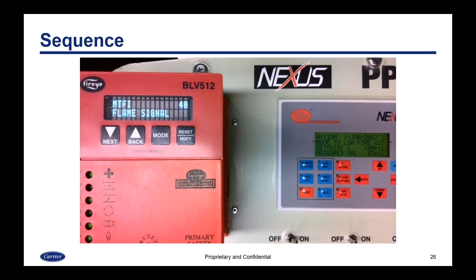So that's one thing to keep in mind, is if you're going to use something like revert to pilot, you're going to want your ignition and your low fire positions to be the same, because it's going to have to be able to light back off there from the low fire position. And that's just an option you can choose to use if your Flame Safeguard supports it. So now it's going to post-purge. It's been shut off, and it should end up at standby when the post-purge is complete.